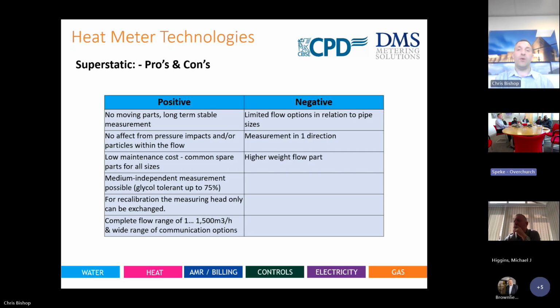One flow direction. Ultrasonics act in such a way, something called bidirectional flow, so backwards flow, a bit of an alert, a bit of an alarm. It's very rare on heating systems, but it's there for water systems where you have ultrasonic meters, with regards to water utilities that sometimes have back flushing and stuff like that, and they want to log what is relevant for the system itself. Because there's a bit more design in the body of the meter, there's obviously more weight involved. Really, 5 to 10% more weight is not a massive difference at all, but, like I say, that's in relation to the design of the manufacturers.